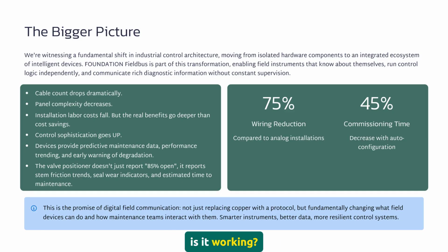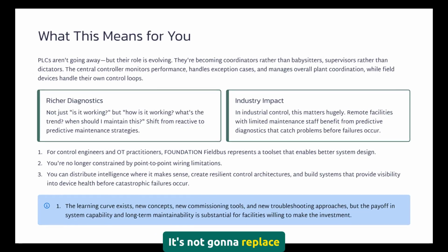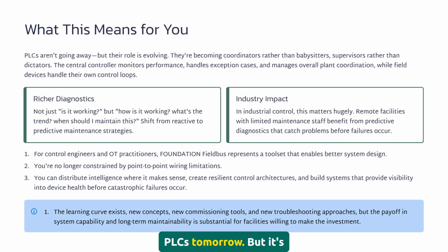But how is it working? What's the trend? When should I maintain this? Cable count drops. Panel complexity drops. But your control sophistication, that goes up. It's not going to replace PLCs tomorrow. But it's reshaping what a PLC actually has to do. Instead of babysitting every instrument, the PLC becomes a coordinator, a decision maker at a higher level. That's actually a better use of engineering time.